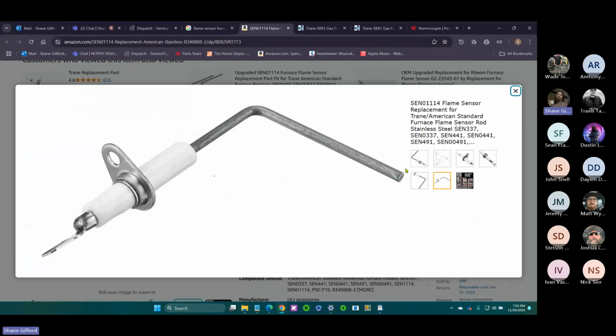This thing produces a very particular voltage back to the control board. Until we hit that voltage, or if we don't hit that voltage, it's shutting everything off. If you do hit the proper voltage, then your flame should stay on and your gas burners will be a go, because you've proven flame. Hey, guess what? We got flame. Go ahead. Let's roll. This thing will make your system work, or it won't let your system work. And it's the most common thing.